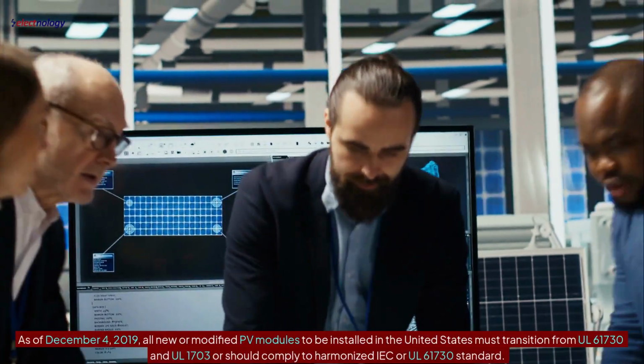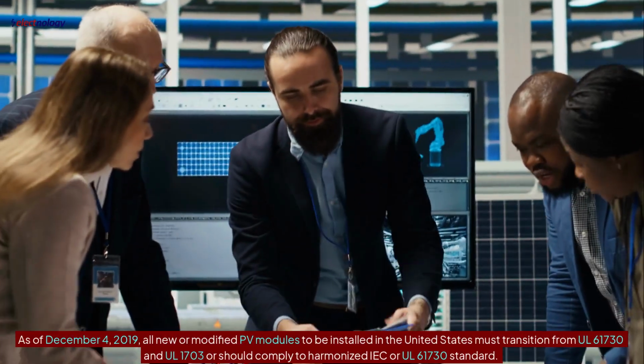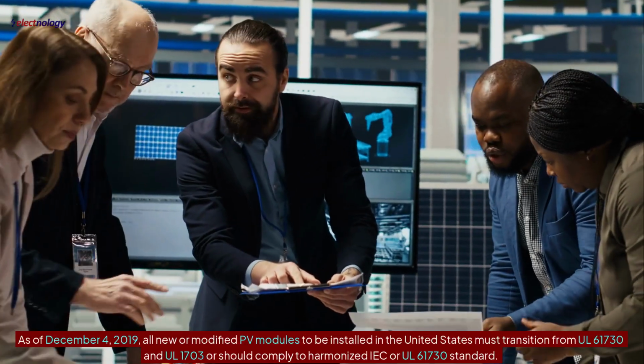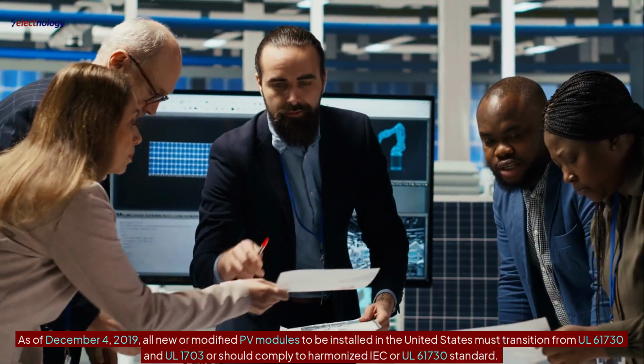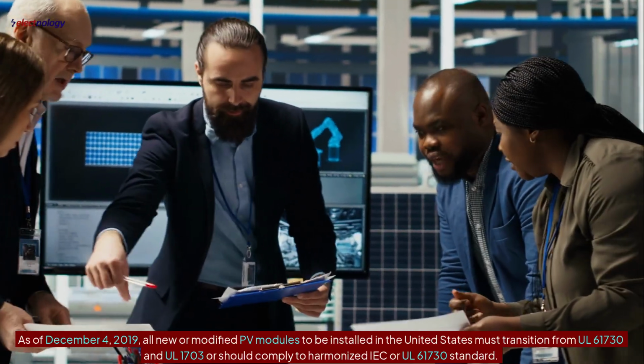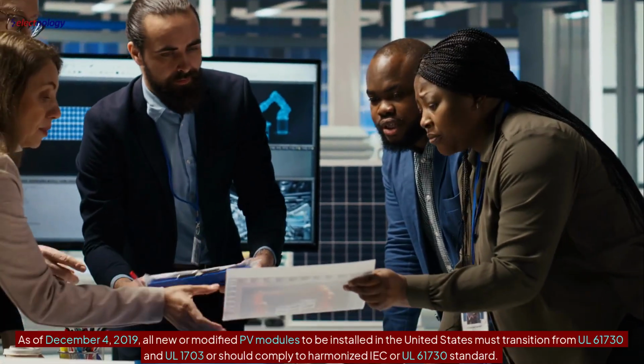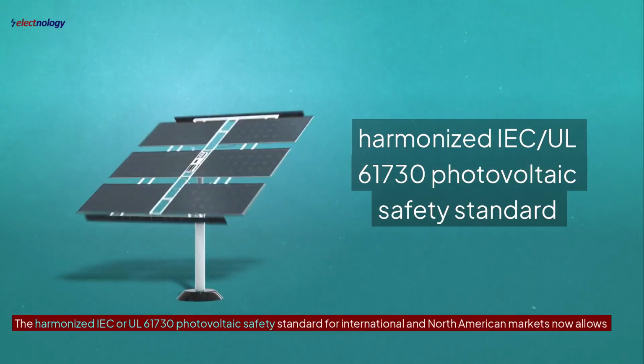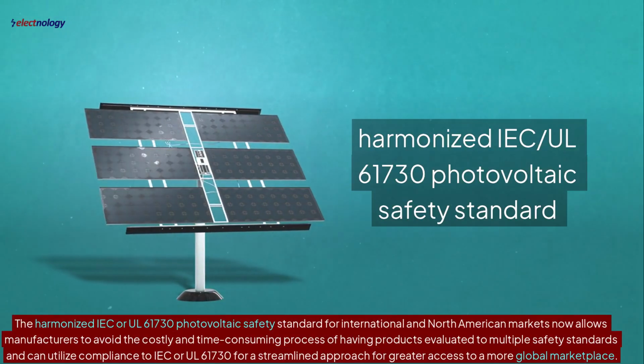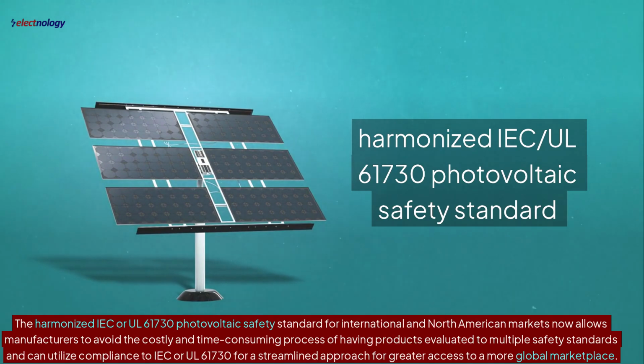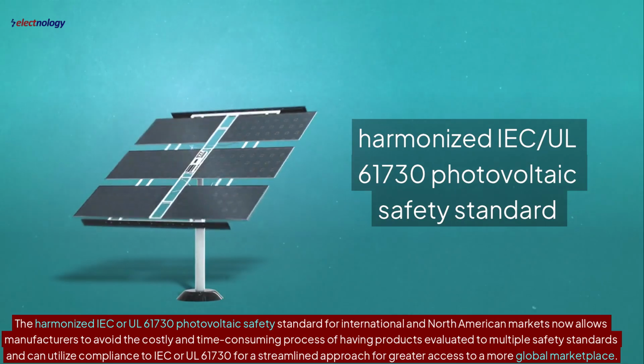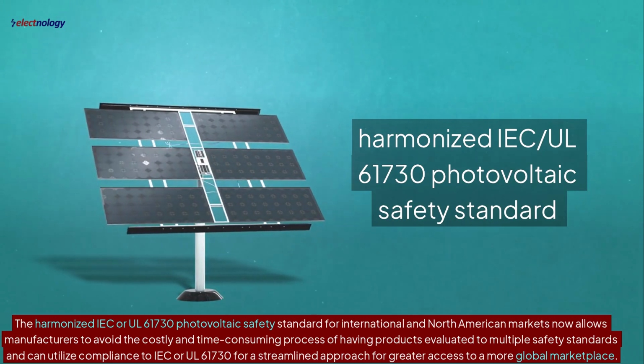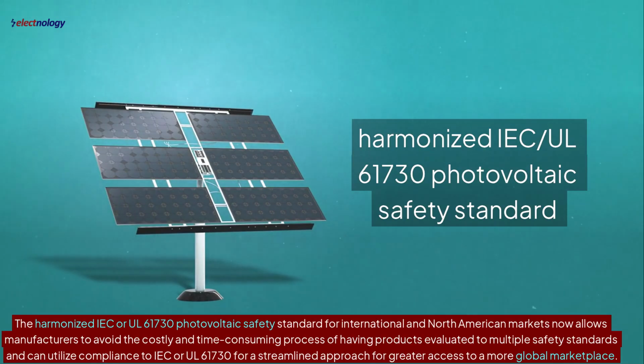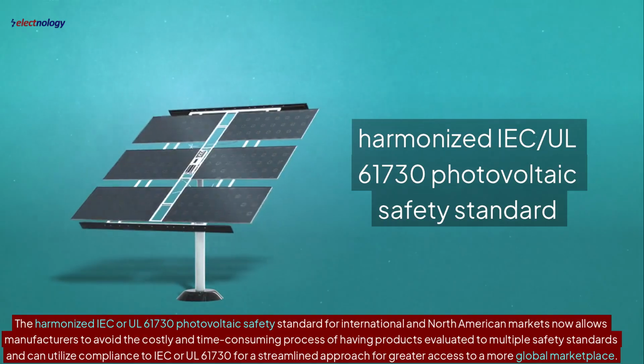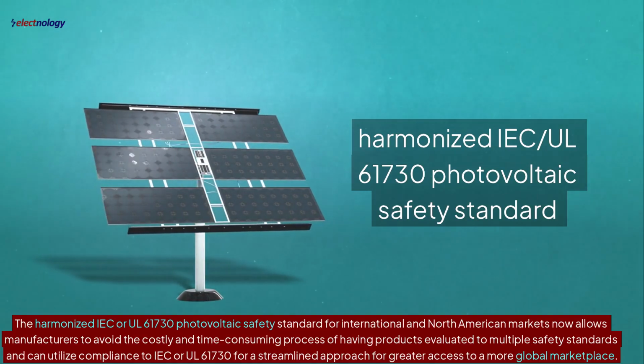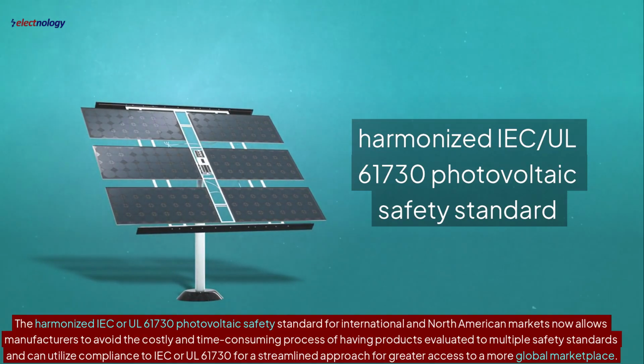As of December 4, 2019, all new or modified PV modules to be installed in the United States must transition from UL 61730 and UL 1703, or should comply with the harmonized IEC or UL 61730 standard. The harmonized IEC or UL 61730 photovoltaic safety standard for international and North American markets now allows manufacturers to avoid the costly and time-consuming process of having products evaluated to multiple safety standards, and can utilize compliance to IEC or UL 61730 for a streamlined approach for greater access to a more global marketplace.